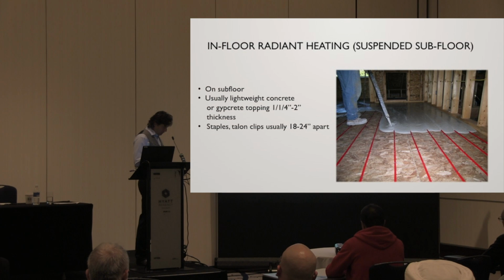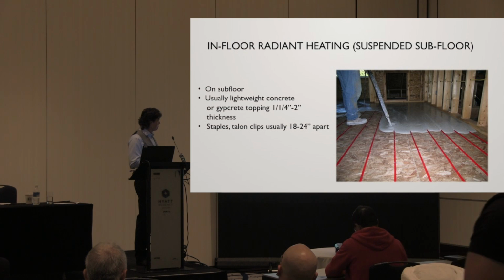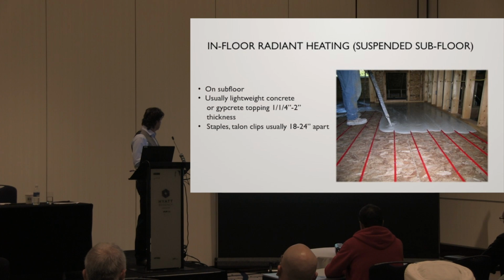Of course, we need some cover over the pipe. In this case, this pipe is 1/2 inch, which means it's 5/8 OD, and here we have staples. So that's another 1/8 right there. So we need to have some cover over this pipe, at least 1/2 inch of cover. I'd rather see 3/4. So do what you will with that. I know mostly everybody in this room has probably done this 100 times. Okay, fastening. So in this case, it's staples. You could use Talon clips if you want, and we'll see those in a picture later on.